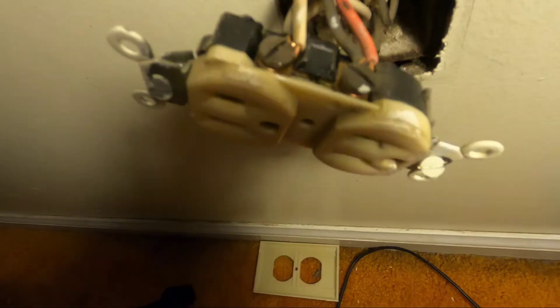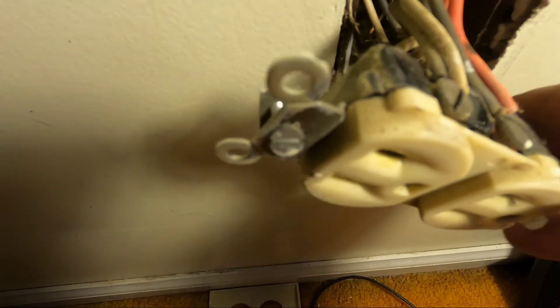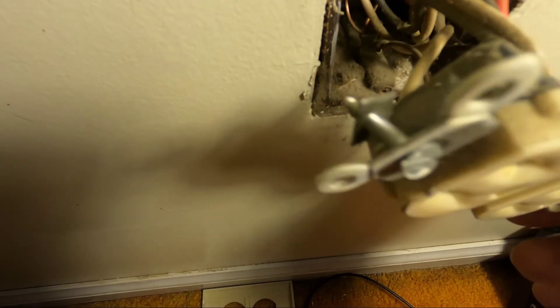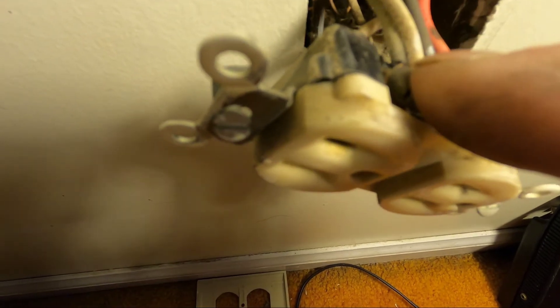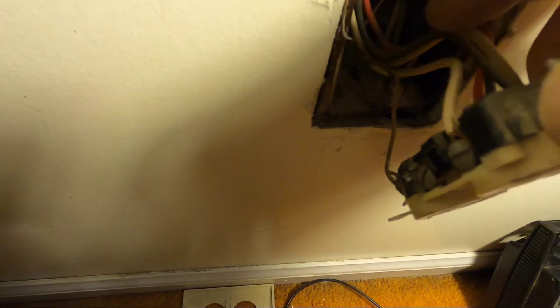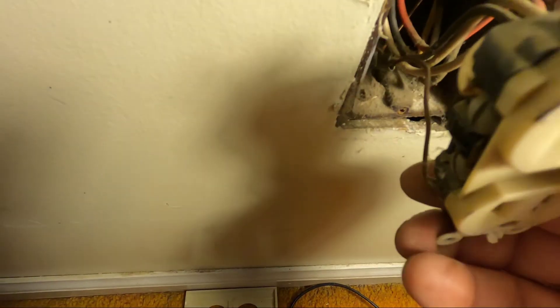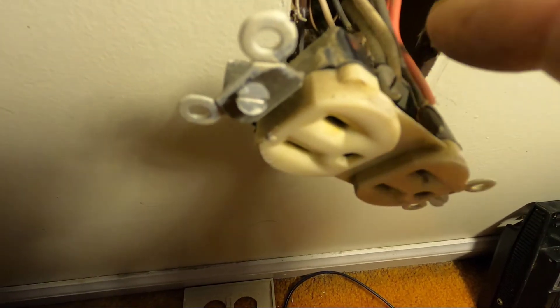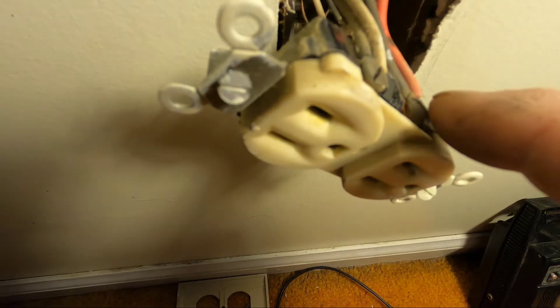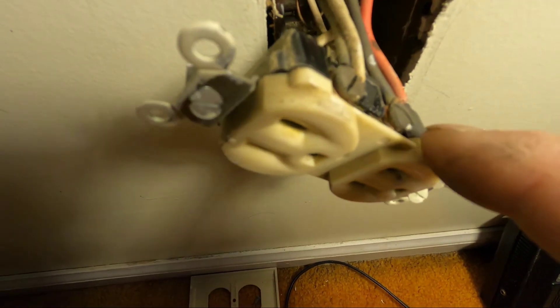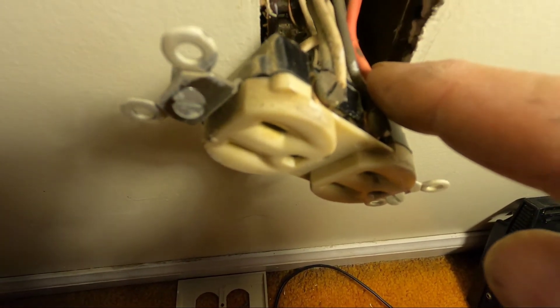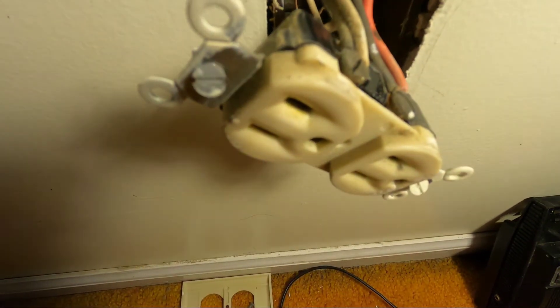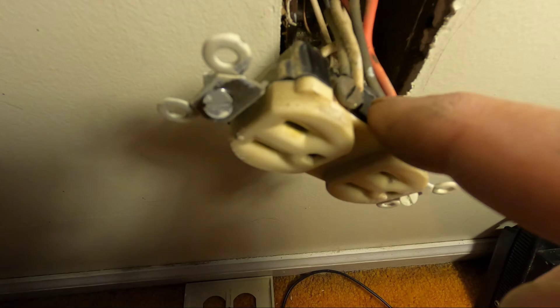Now, you can see over here, you have a white wire coming in, and a red and a black. What's happening here, normally the feed would come in from the top and go out through the bottom. But typically, the hot leg would be coming in, and then it would go through the outlet and back to the box. Now you have two hot wires. One's the feed, and it's like a daisy chain. This one is being fed by another outlet.